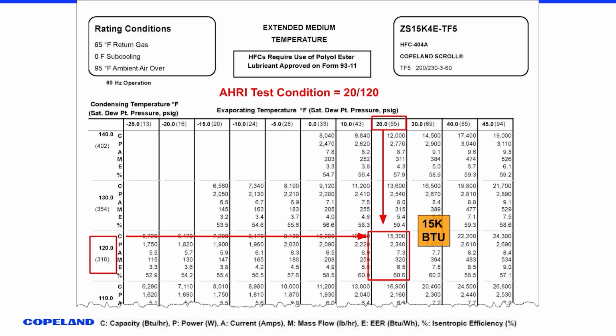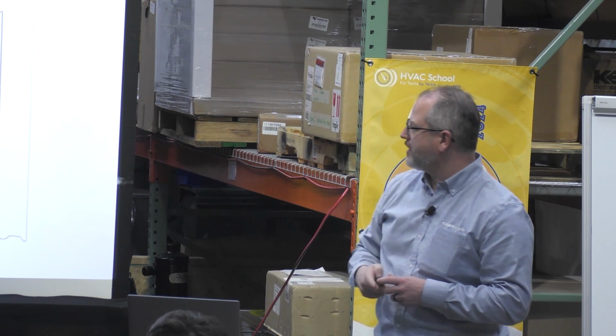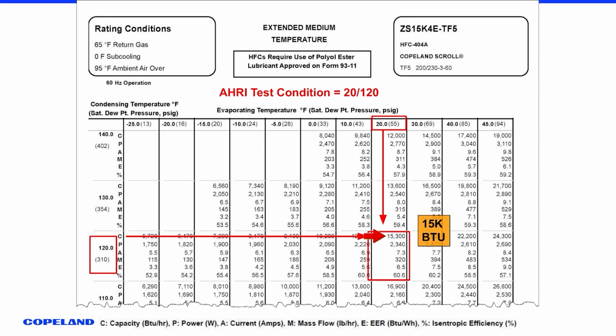Okay, so as an example, if you look at the numbers, so we go to 20, and the numbers in parentheses, that's the actual pressure. Okay, so if you went to your gauges, it would say 55 psig. Okay, now we go to the high side, 120, and our gauges would say 310 psig, right? So we bring those together, and we get 15,300 BTUs. Does that look familiar? Look at our model number.